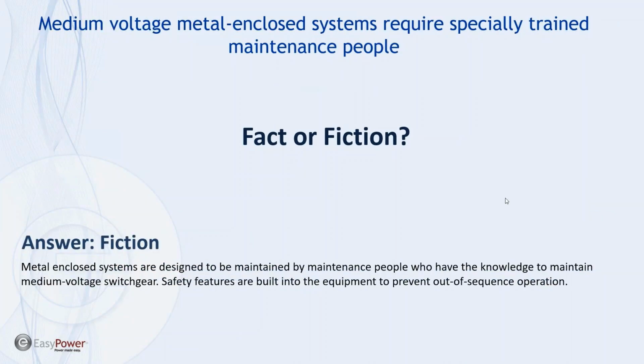Next myth: medium voltage metal-enclosed systems require specially trained maintenance people. Our systems and most metal-enclosed systems are designed to be maintained by maintenance people who have a knowledge of maintaining medium voltage switchgear. So if the maintenance people can understand and maintain medium voltage switchgear, they can maintain a capacitor bank or harmonic filter bank. It does not take especially trained maintenance people to maintain metal-enclosed systems. They're designed for that purpose.